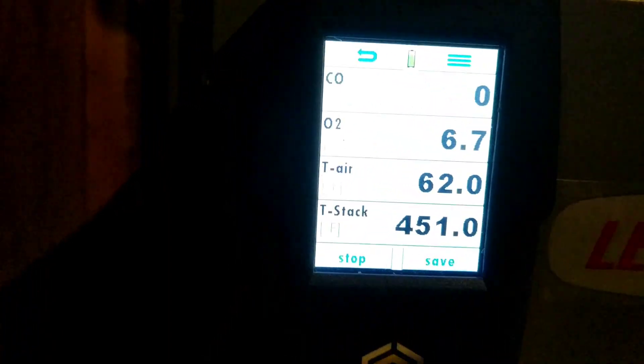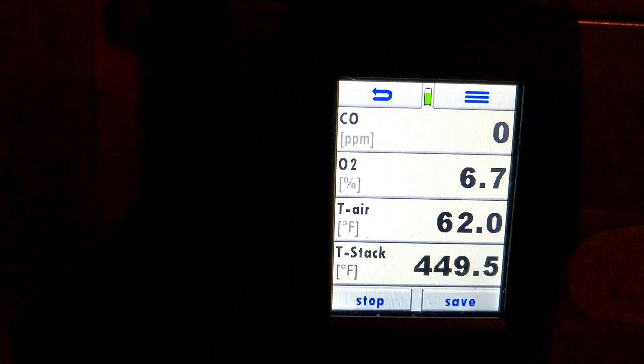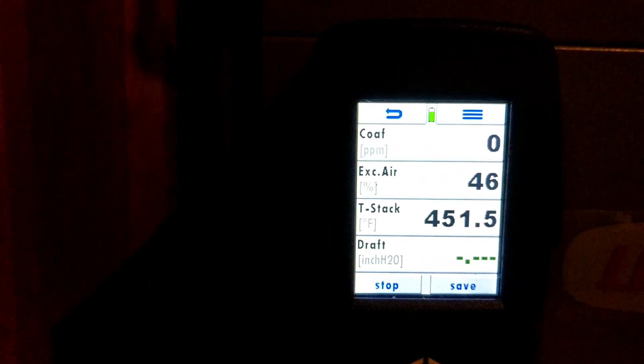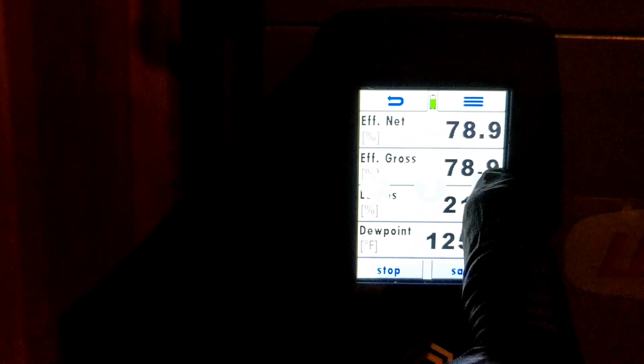We're running through everything here. Machine's running, we've got no CO. Oxygen is sitting good, temperatures in the stack are good. Excess air is okay — everything seems to be running well.